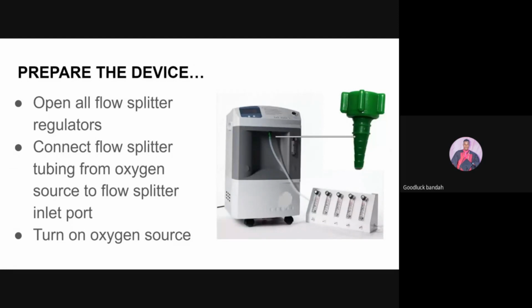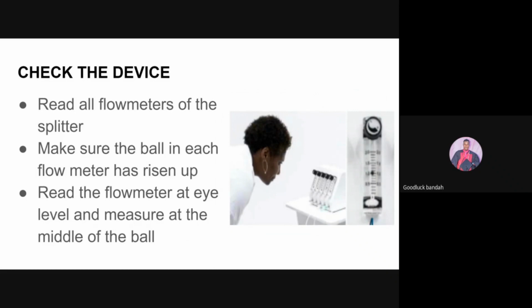Now let's look at how we can check our oxygen splitter. You have to read all the flow meters of the splitter. Make sure that the balls in each flow meter have risen up. Otherwise, you may have blockages in the outlets of the oxygen splitter. If you have blockages, you want to have your balls risen up. In that case, it's time to do some maintenance to remove the blockages. It is also important to know how you can read your flow meter. You have to take the reading of the flow meter at eye level and measure at the middle of the ball. If you are using a flow meter which has a ball, it's always recommended to take your reading at the middle of the ball.